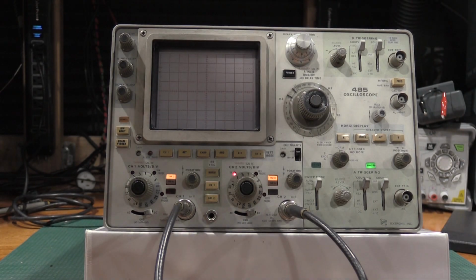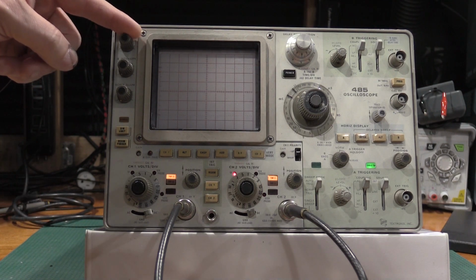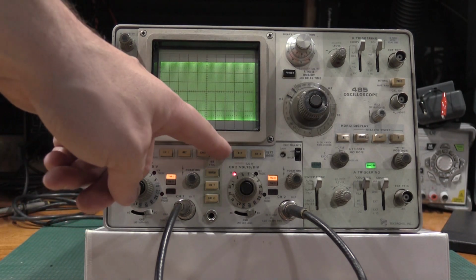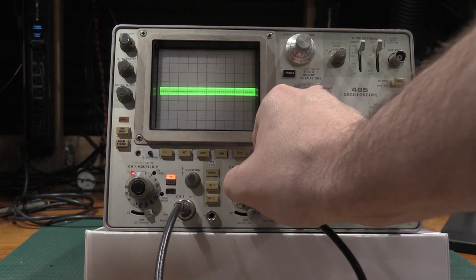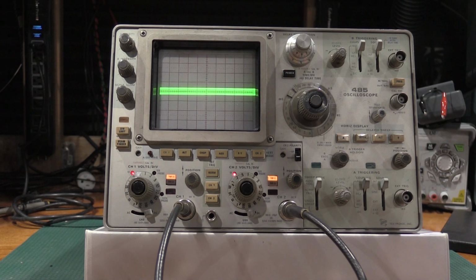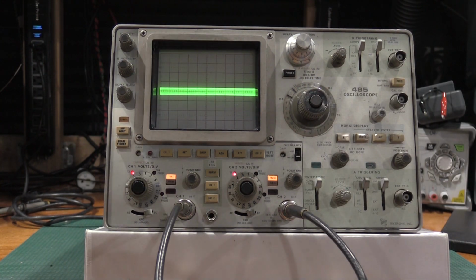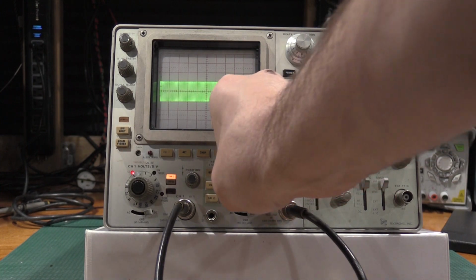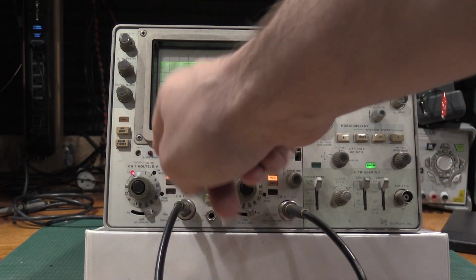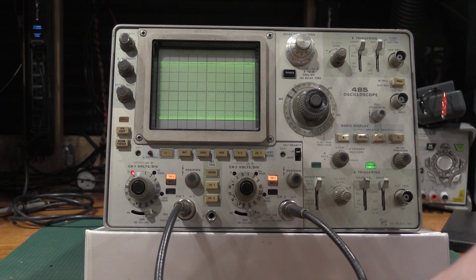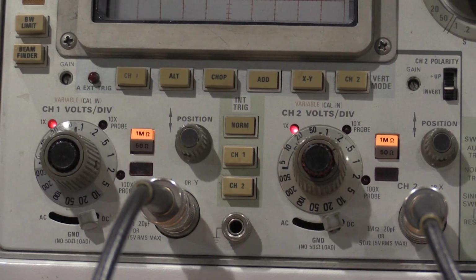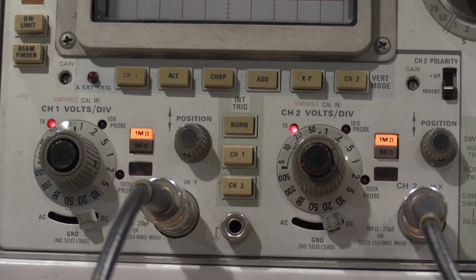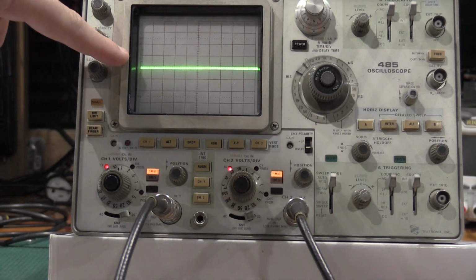Okay, after completely rebuilding another attenuator and getting it in there for channel 1, we're ready to try this again. 6 divisions of display, add invert, and then we want to make this as small as possible. Oh, yeah. Got to reset it up. Part of my problem was I was checking it on the wrong vertical scale. It needs to be at 20 millivolts, not 0.2. Man, this thing is arguing every step of the way. However, there's our common mode rejection ratio, and we are good to go.